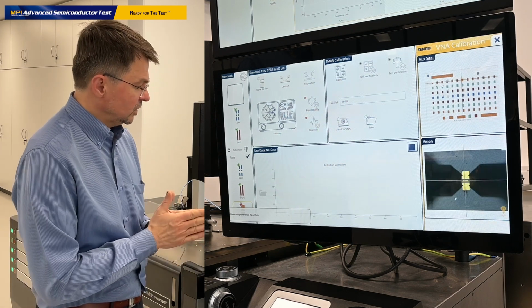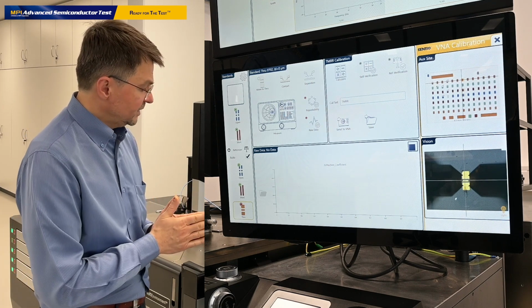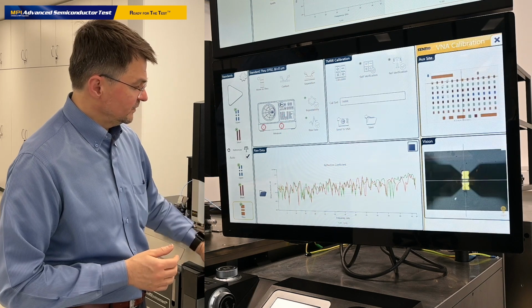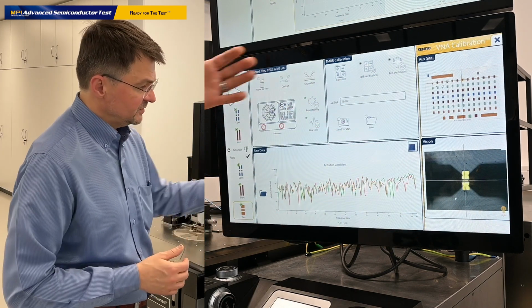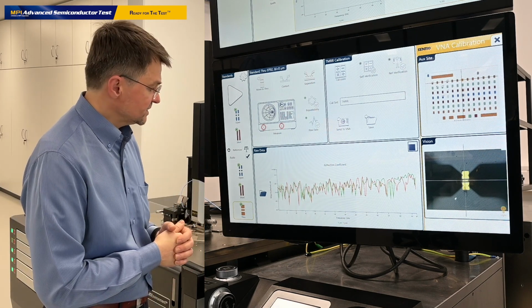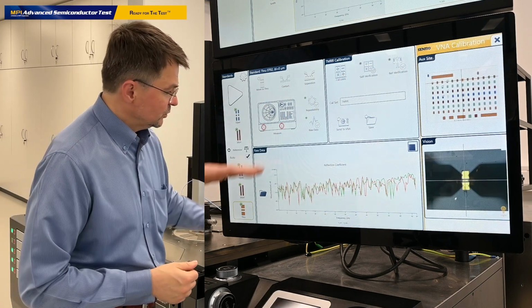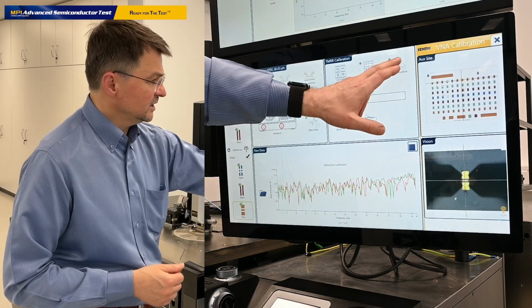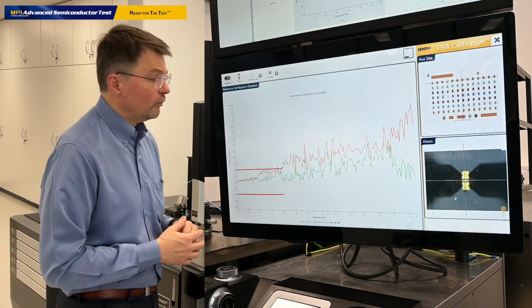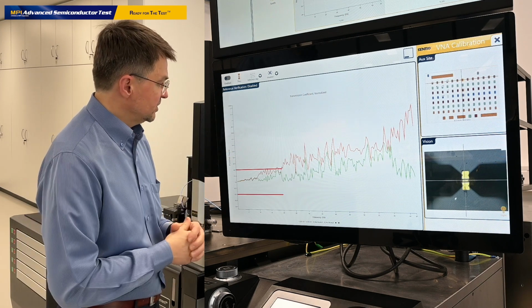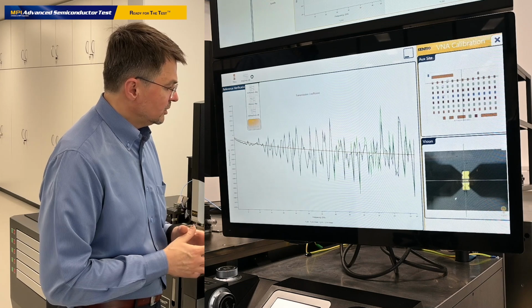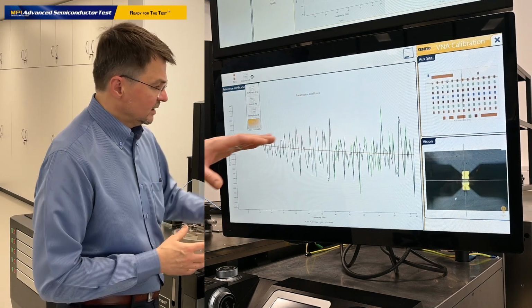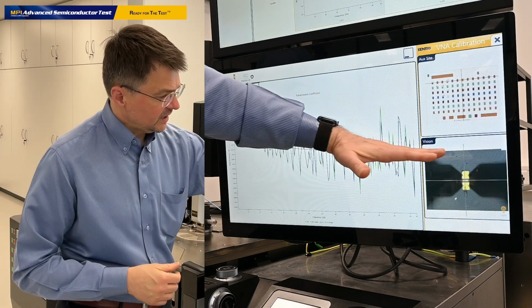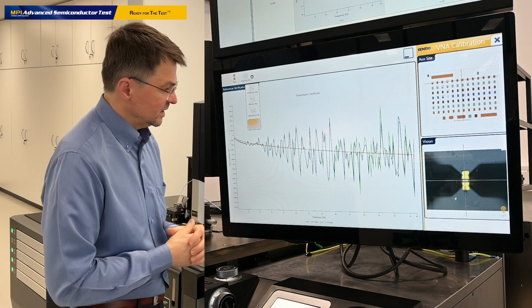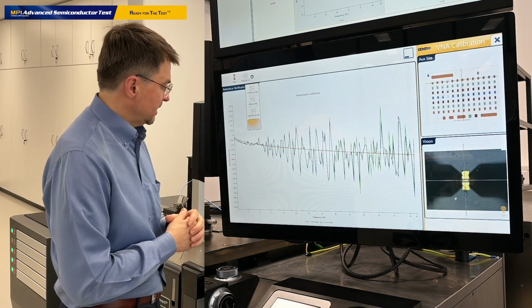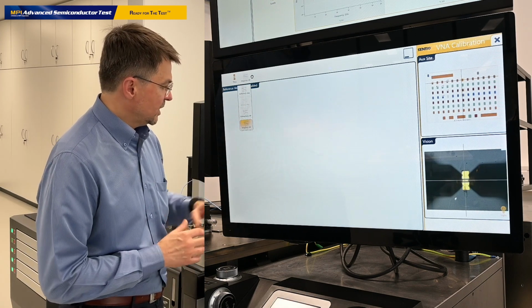Let me give you an example of how to verify the quality of the calibration procedure, for instance, based on the measurement of the through standard. It is the same user experience as you already learned from the execution of the calibration process. This is the standard, the data associated with the standard, our golden reference element. These are the raw data, but when we look into the data measured after the calibration process, we see some variations here. Let us go just one by one. Usually, when we look into the data measured after the calibration process, we see a straight line, which is the model of our standard that we used for that, and these are the corrected data, for the magnitude as well as for the phase.